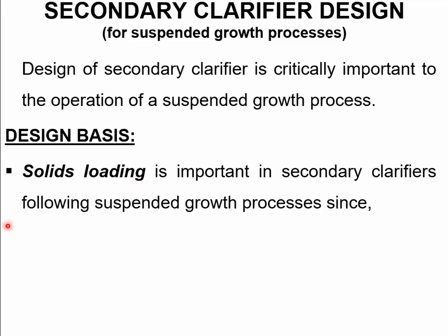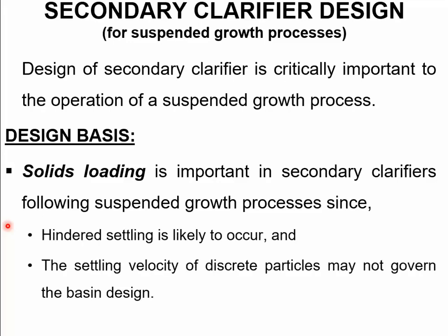Solids loading means how much amount of sludge or how much amount of solids, basically biomass in solids form, are being applied to the surface area of a secondary clarifier. So hindered settling, a type 3 settling is likely to occur, and the settling velocity of discrete particles may not govern the design basis. This was the design basis for primary clarifier.